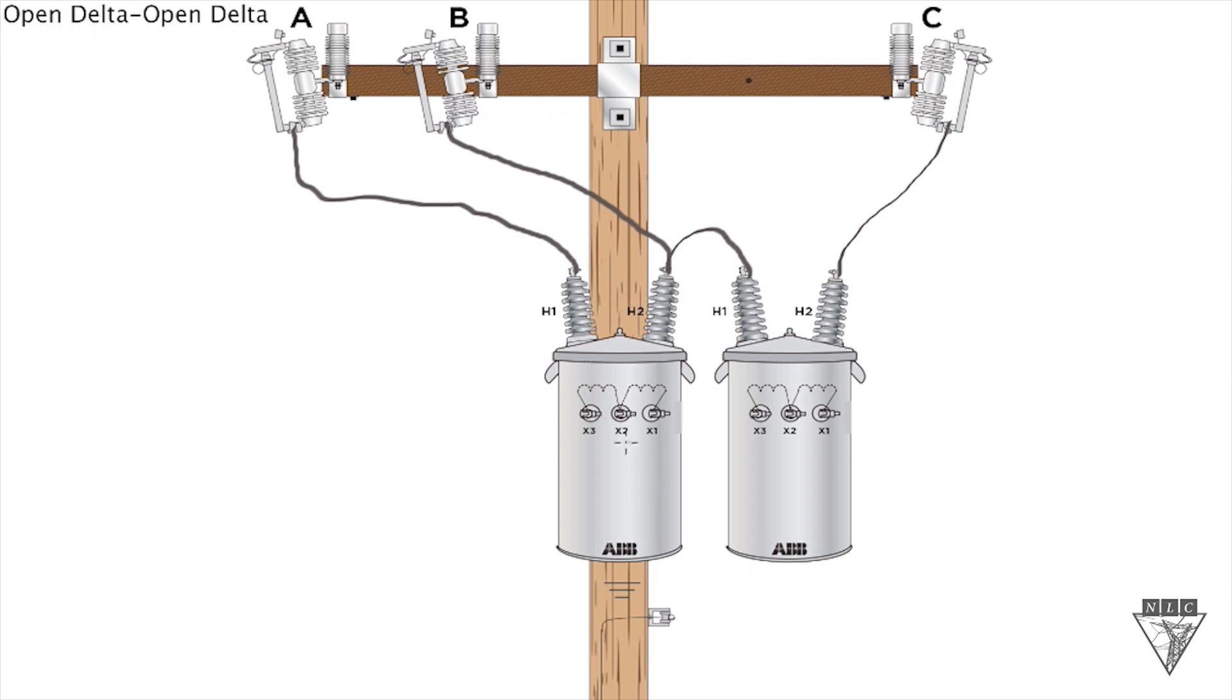Let's go to our secondary connection. On the secondary side, we're only going to utilize one of the X2 bushings and we're going to do it on the center one. Take it straight down to ground and that's our secondary neutral connection.